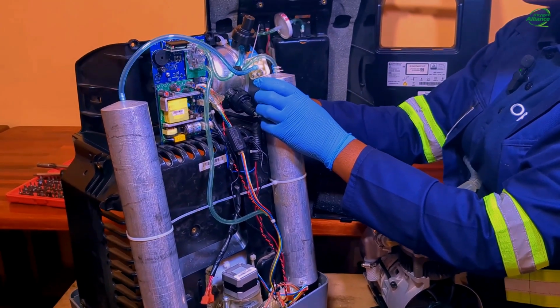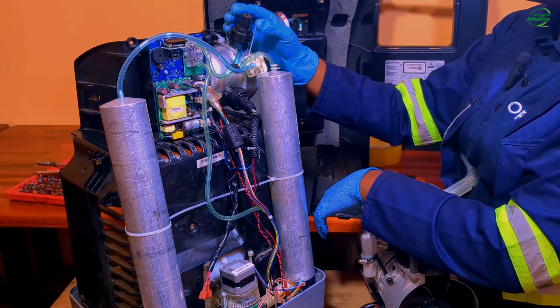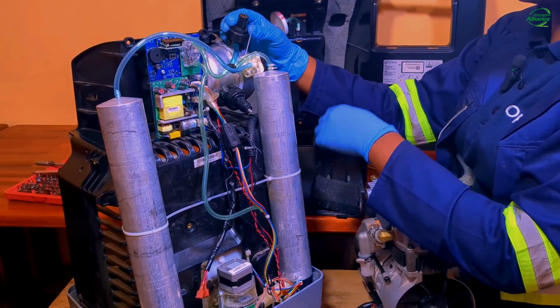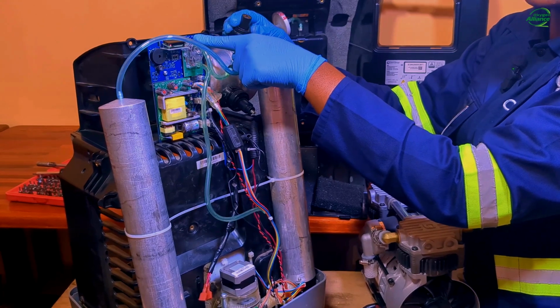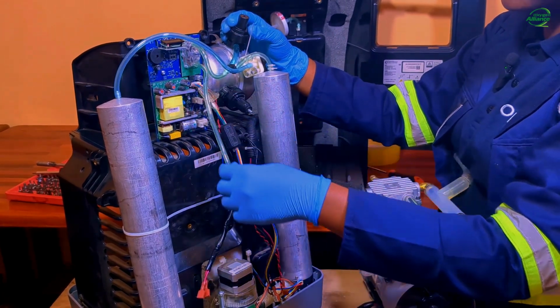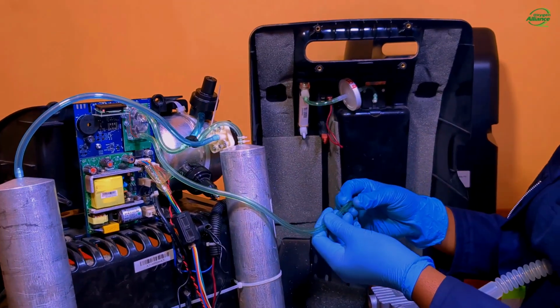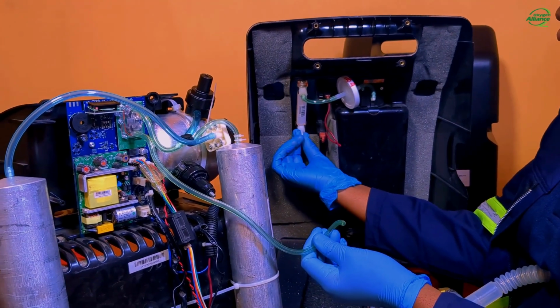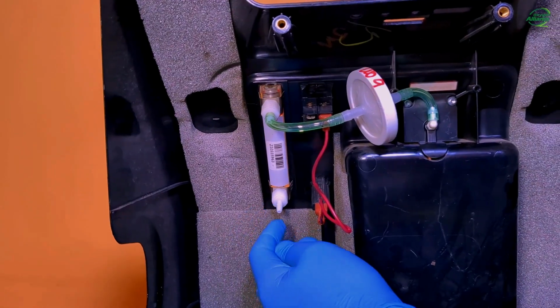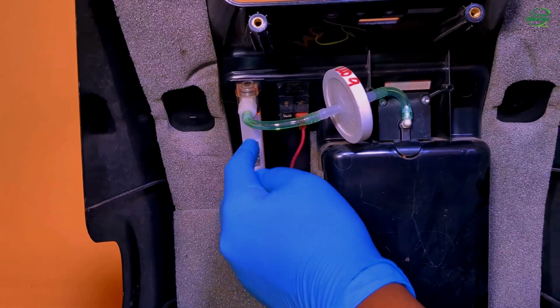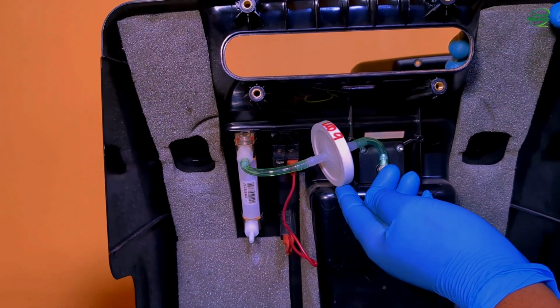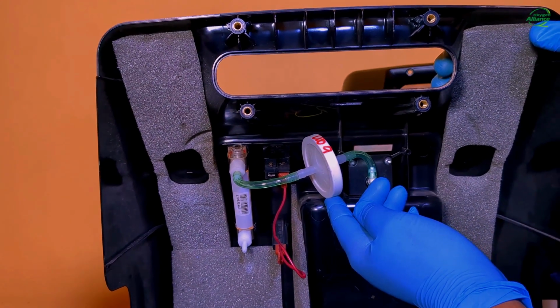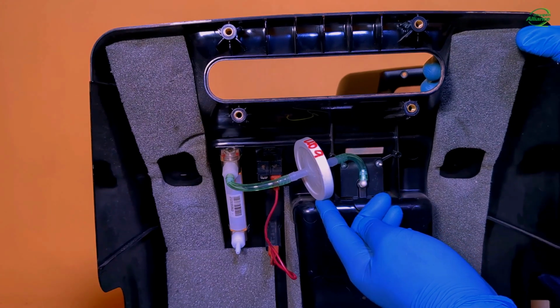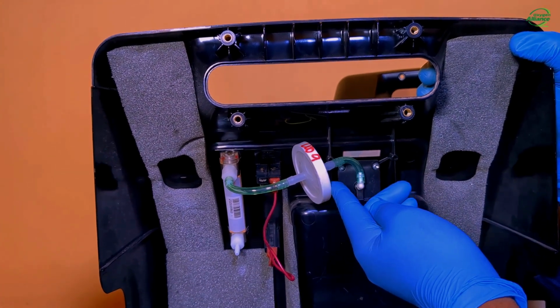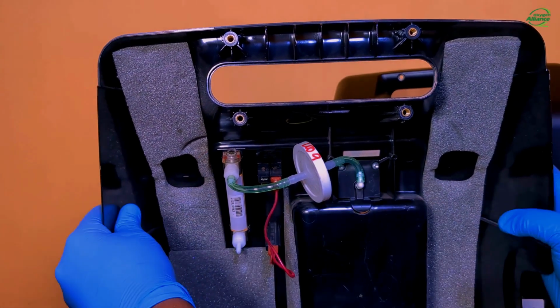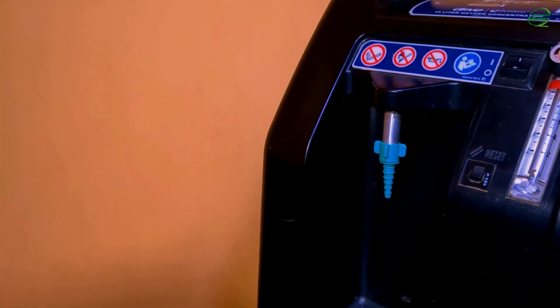And from the product tank, the oxygen will be regulated with this pressure regulator, going through the oxygen sensing device and out through this tubing. This tubing is the one that is connected here at the flow meter. And through the flow meter, it goes out this pipe to the bacterial filter.